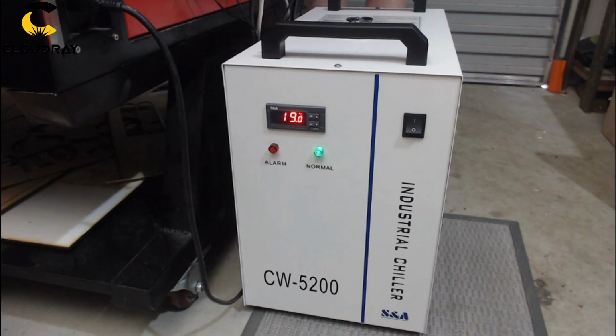So one thing I do want to show you is the water alarm. This laser machine doesn't have a water flow sensor that will alert me when the water flow is stopped. The water chiller, however, has a built-in alarm. So if I just go to the back of the machine here and occlude one of the hoses, we should get an alarm that will sound to alert us that the water is not flowing correctly. And as soon as the water flow is restored, the alarm will stop.